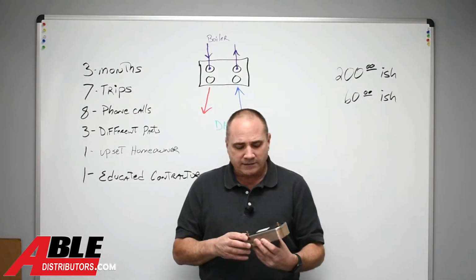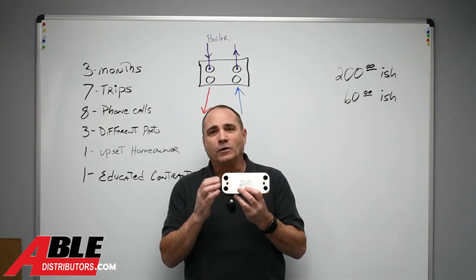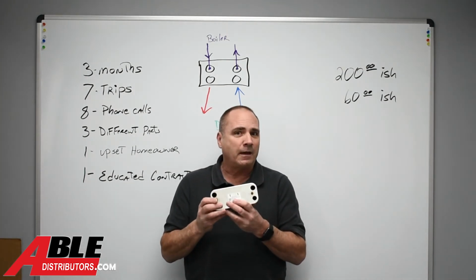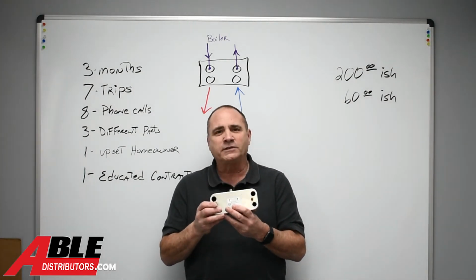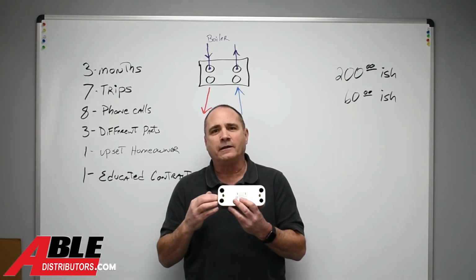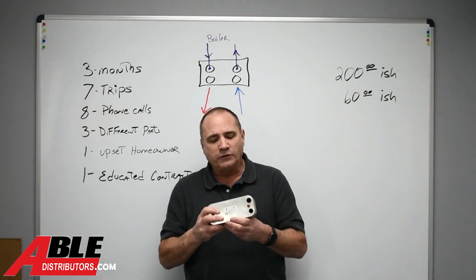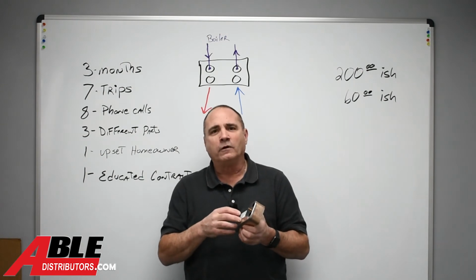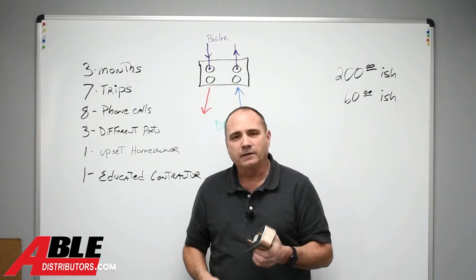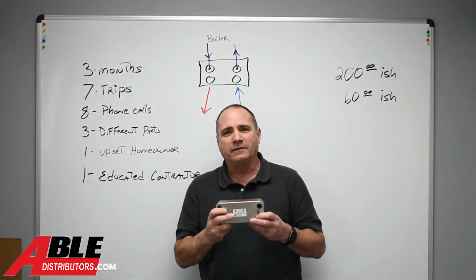I'm not saying the only time you've got to worry about it is when you have a flat plate heat exchanger in a combi situation. I'm saying get that sludge and dirt out of there all the time. When we took this out and turned it over, literally mud came out of it. That's how bad the system was.